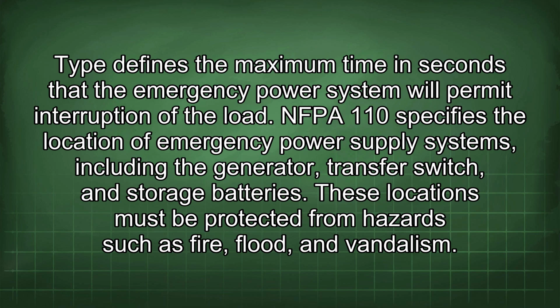NFPA 110 specifies the location of emergency power supply systems, including the generator, transfer switch, and storage batteries. These locations must be protected from hazards such as fire, flood, and vandalism.